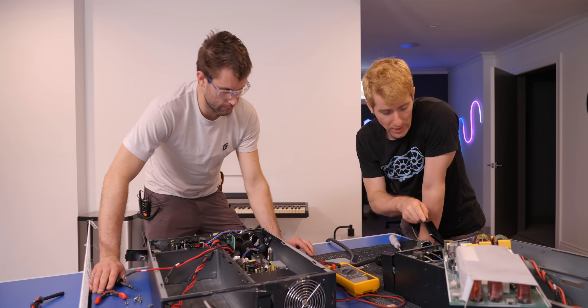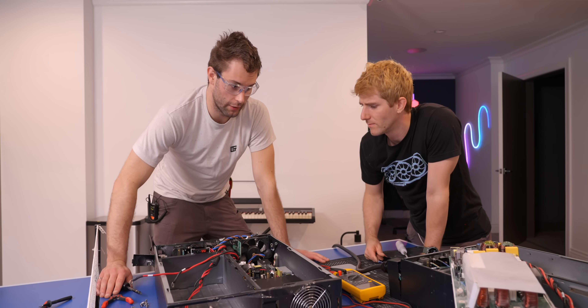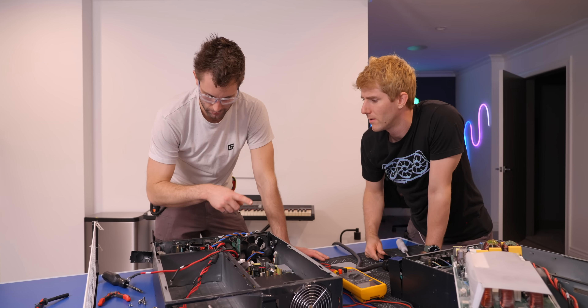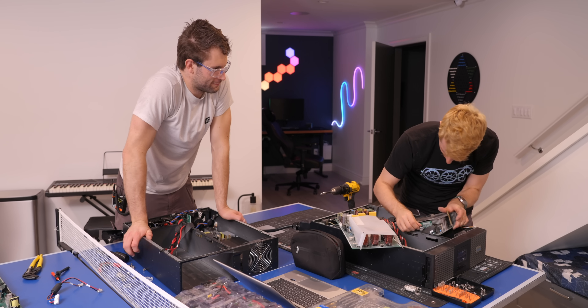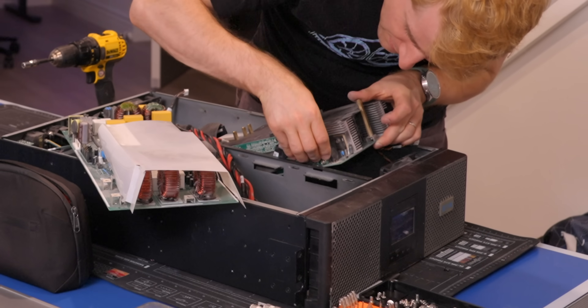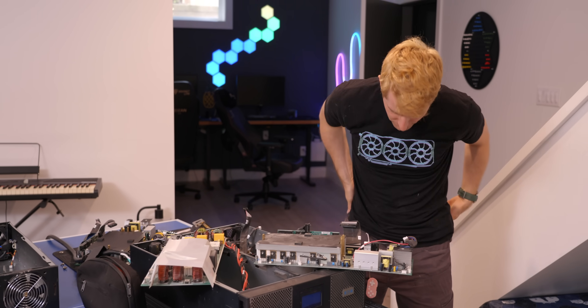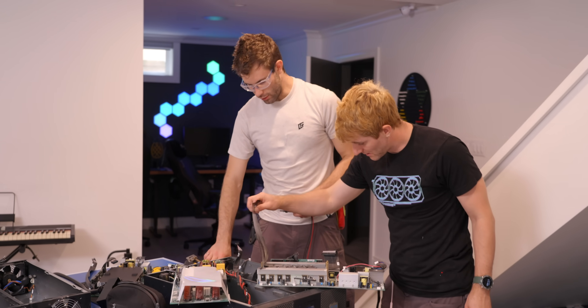Before we tear them both completely apart, what are the odds that a short in the breaker would have caused those fuses to blow? It would have had to have been a short between the breakers, because one breaker is a single phase of power — it would have to short across two phases for those to blow. These should break if anything downstream fails, but if that were true, why would you need fuses anyway? Because you're dealing with enough power that if something goes wrong, your board's going to melt. We found another dead fuse, this time on the bottom board. All the fuses blew. The system works.